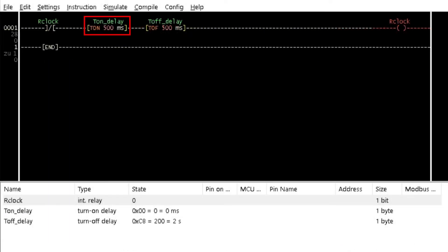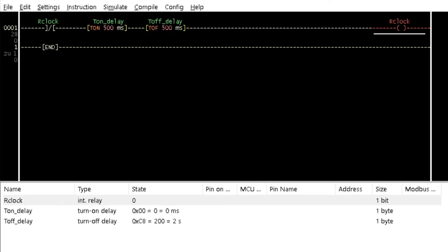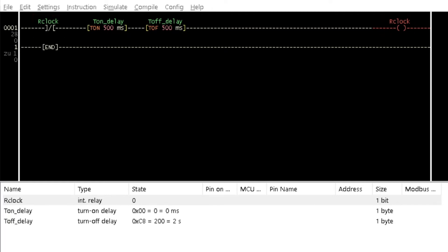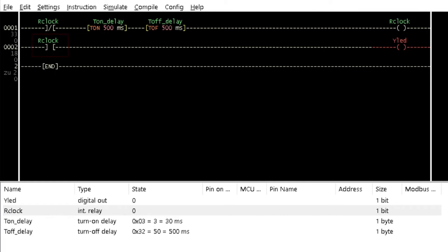Insert a turn on delay and a turn off delay timer between a contact and a coil. Assign a time interval of 500ms to both timers. Name the contact and the coil as 'clock'. Change the contact and the coil to internal relays and negate the contact. Insert a rung below rung 1 and insert a contact and a coil in it. Set the contact to be an internal relay and assign it the variable name 'clock'. Name the coil as 'Yled'.